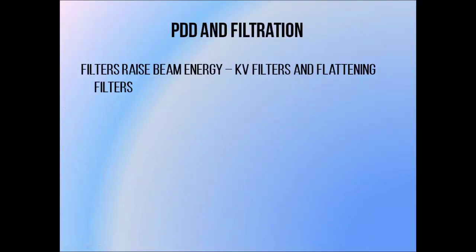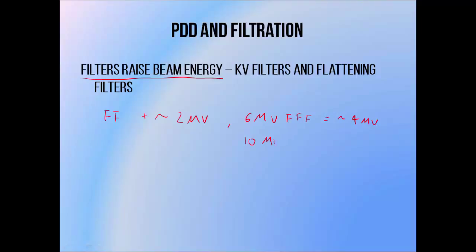Beam filtration affects megavoltage beams as well, normally as an effect of the flattening filter or any wedge filters placed in the path of the beam. Passing through a flattening filter results in beam hardening — an increase in the effective energy of the beam due to preferential attenuation of low energy photons. Passage through a flattening filter raises a beam's effective energy by about 2 MV. So flattening filter-free beams will have PDD curves similar to a beam of slightly lower energy: a 6 MV FFF beam produces a PDD similar to a 4 MV flattened beam, and a 10 MV FFF beam produces a PDD similar to an 8 MV beam.